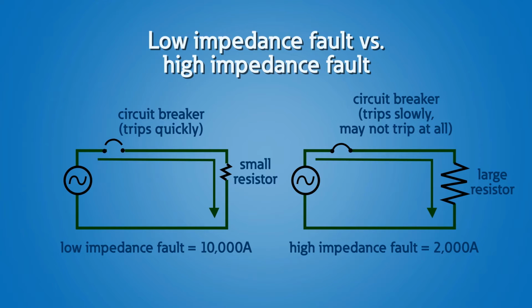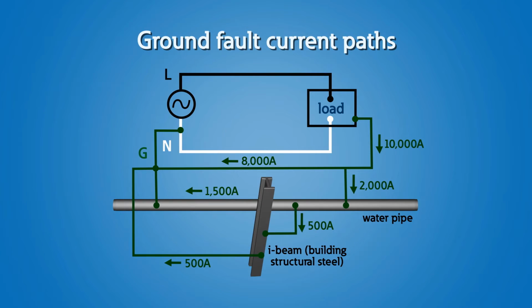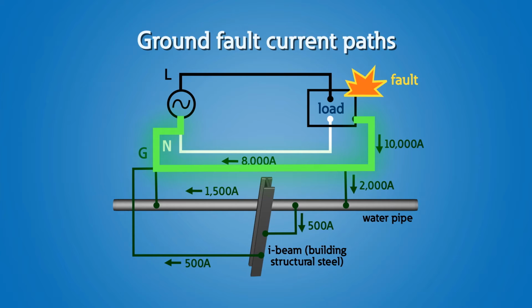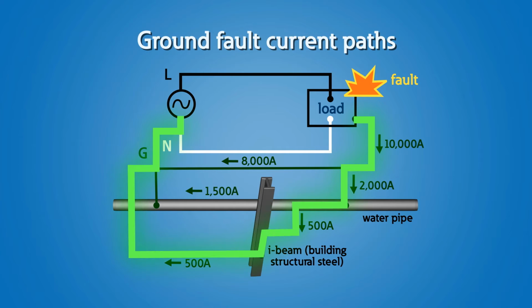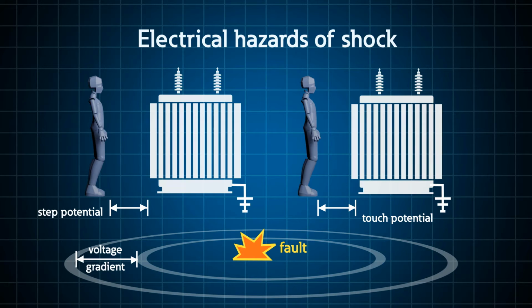Now, you want that impedance to be as low as possible because we want to drive the fault current as high as possible. We have to understand the basic principle that ground fault currents will flow anywhere they can get a chance to. We're not going to guarantee that only the fault currents will flow through the equipment grounding conductor. That's why we can't make the mistake of thinking that this grounding and this bonding will prevent someone from the electrical hazards of shock. When we talk about those hazards of shock, we want to reduce our touch potentials or our step potentials. We want to keep everything at the same potential and be like that bird on a wire.